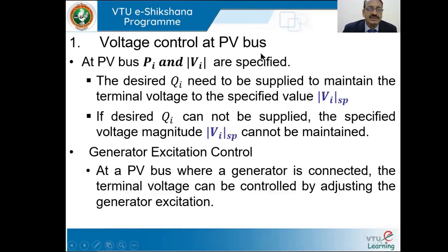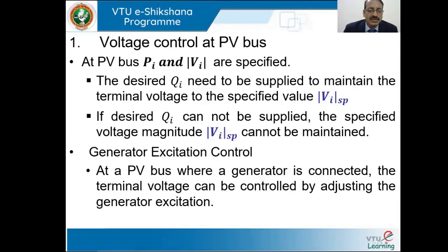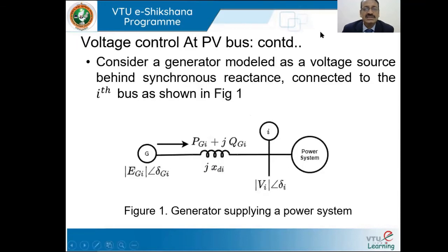Voltage control at a PV bus: in a PV bus, Pi and Vi are specified. The desired reactive power injection Qi needs to be supplied to maintain the terminal voltage Vi to the specified value Vi_sp. If the desired Qi cannot be supplied, the specified voltage magnitude Vi_sp cannot be maintained. The reactive power requirement at the bus can be supplied by generator excitation control. At a PV bus where a generator is connected, the terminal voltage can be controlled by adjusting the generator excitation.